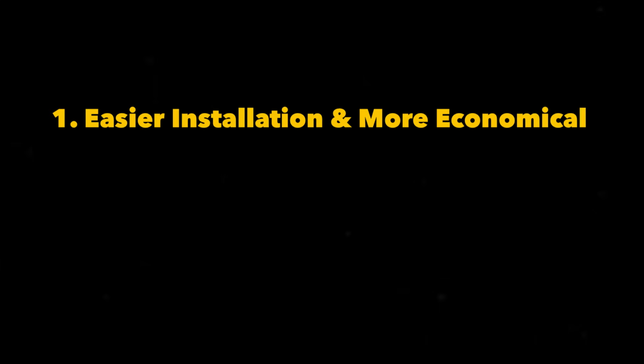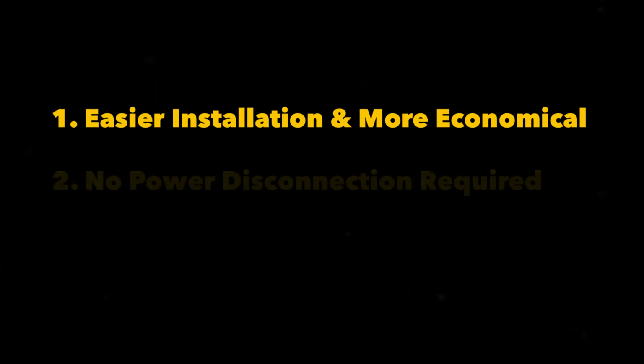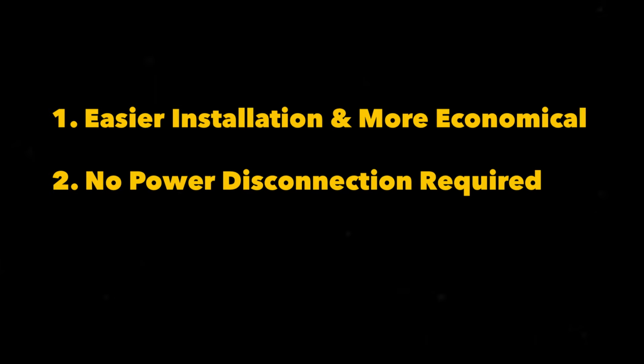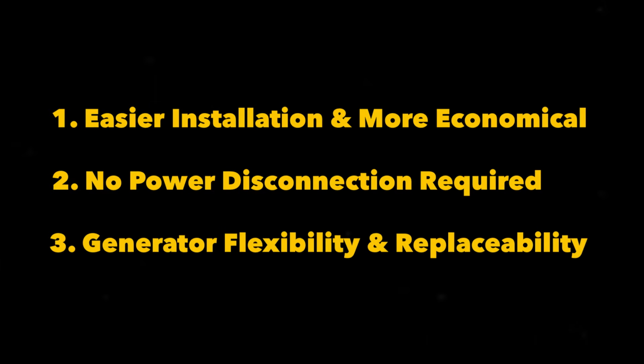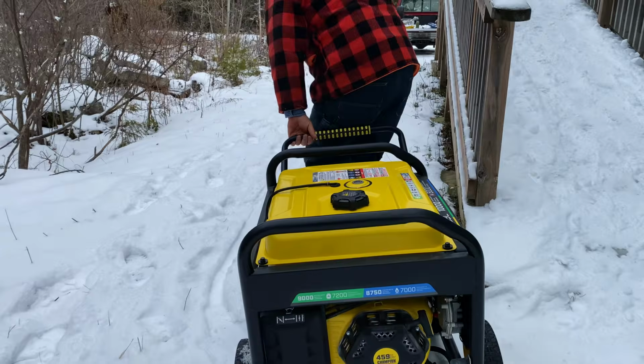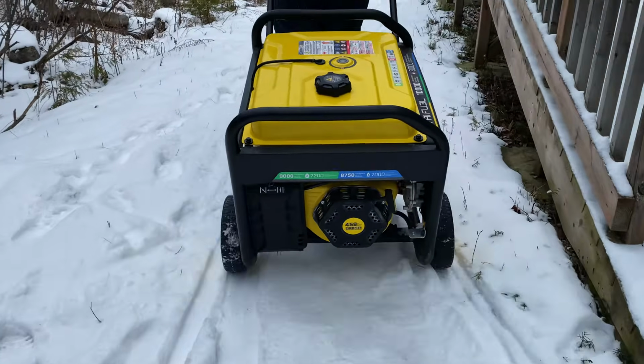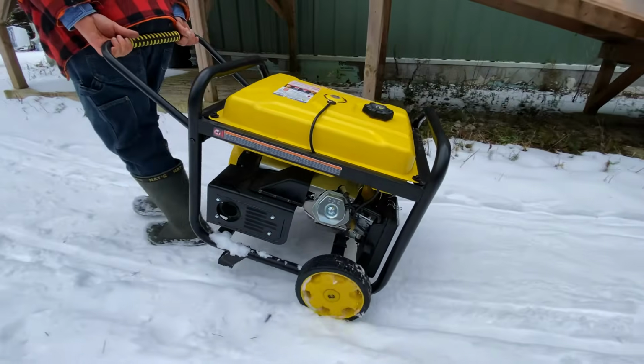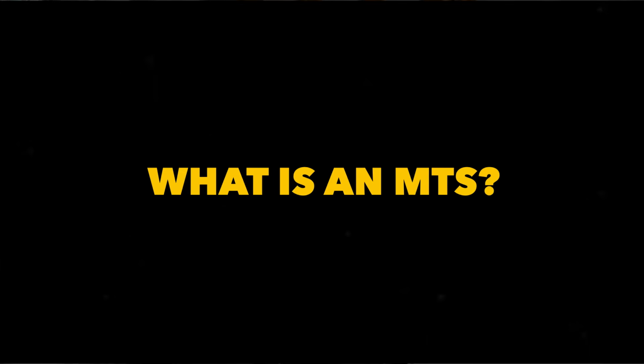Besides being far cheaper than the alternative of a standby home generator, a portable generator connecting to one of these manual switches offers distinct advantages. The system is more economical and easier to install than a stationary automatic standby generator. You don't need to have the utility power to your home disconnected during installation, as with meter-based connection systems, and you can easily upgrade to a larger portable generator in the future if you need it. You can also use your portable generator in other locations when it's not supplying power during a blackout. And if your portable breaks down when you really need it, you can simply swap in another one until grid power returns.